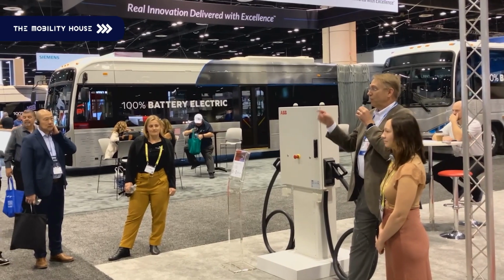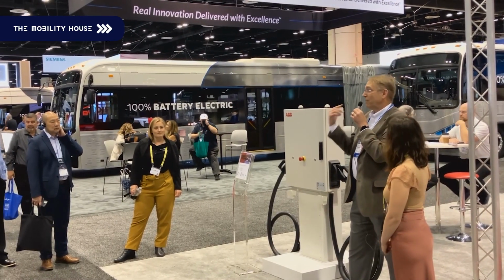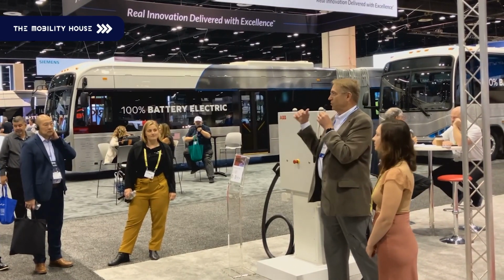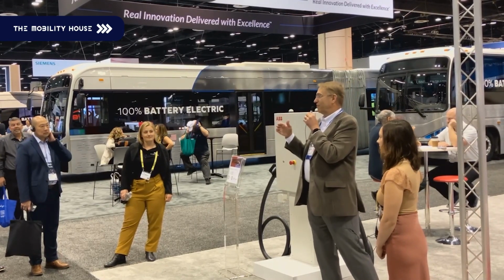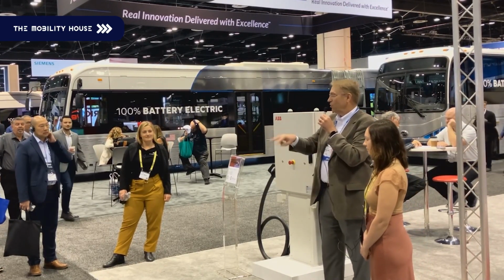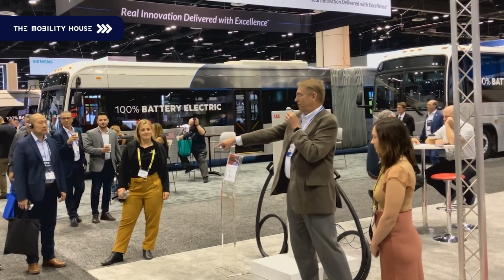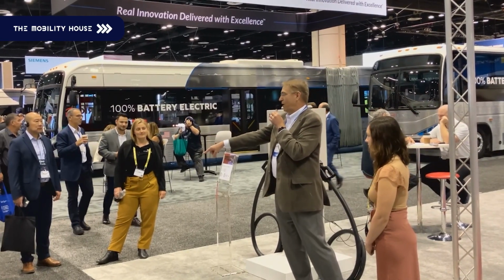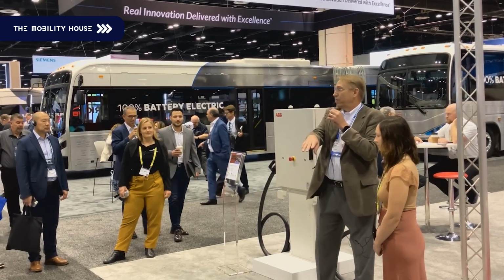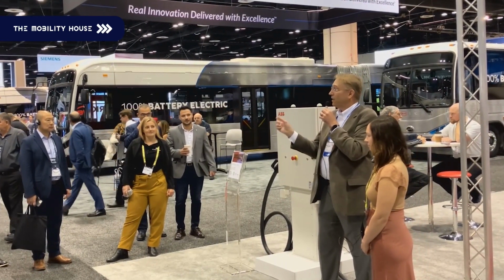But we have the ability to do a matrix switch inside, and that's where we'll take an OCPP command to say let's charge that out - let's put 2 of those 90 kilowatt strings on that outlet to charge at 180 kilowatts now, or put all 4 on that outlet so we charge at 360 kilowatts. It'll have the ability to do that.